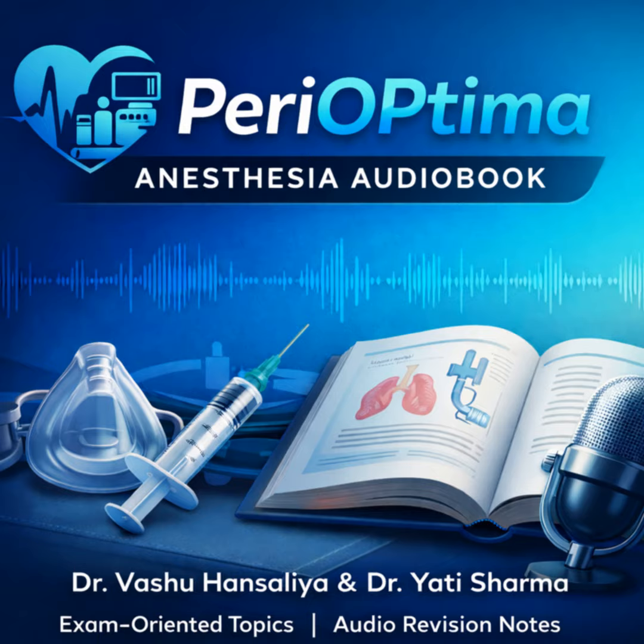And if you identify a susceptible patient, how do you manage them? First, schedule them as the first case of the day. You want the cleanest possible anesthesia machine. What does machine prep involve? You need to remove the vaporizers from the machine. Then you flush the machine with high-flow oxygen, 10 liters per minute for at least 20 minutes, though the exact time varies by machine manufacturer. You must change the CO2 absorbent and the entire breathing circuit.